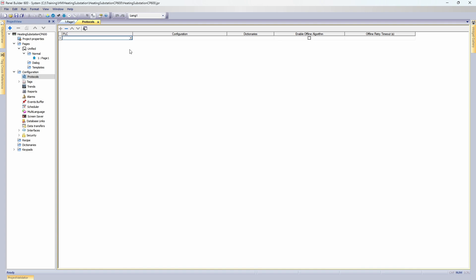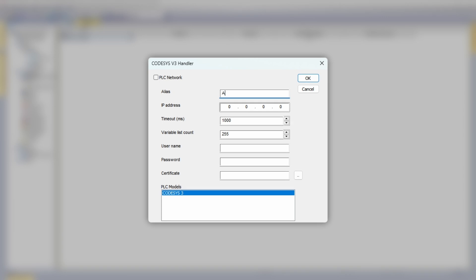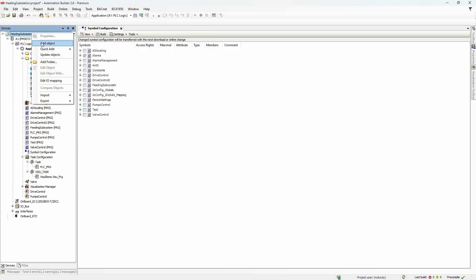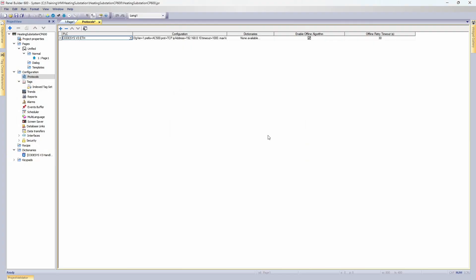Go to Protocols and click the plus button. In the drop-down list, there are two options: CODESYS v3 ETH or CODESYS v3 handler. The second is recommended because it provides authentication and encryption options. If you add it, the alias would be the device name, the IP address is the address of the PLC, and the user password and certificate serve as a security mechanism. That only works if you use user management inside the PLC. I didn't use user management in the PLC application, so I'll show you how it works with the CODESYS v3 ETH driver, which is the same driver that would be added if you started the HMI project from Automation Builder. Save these changes and go to the Tags window.